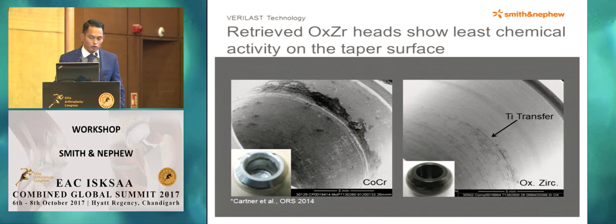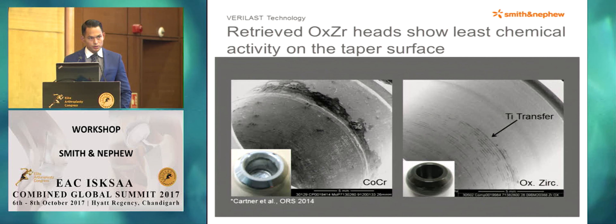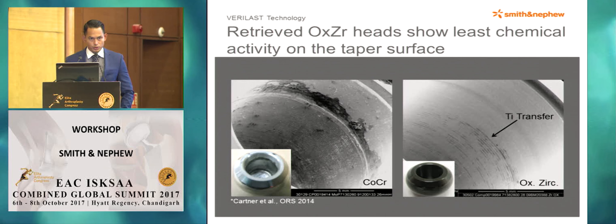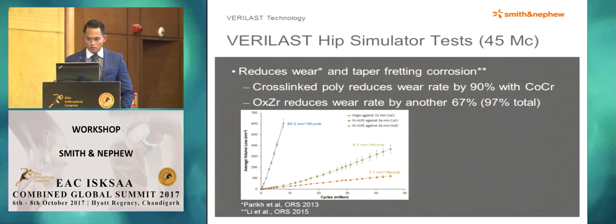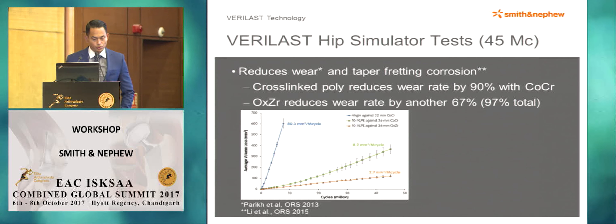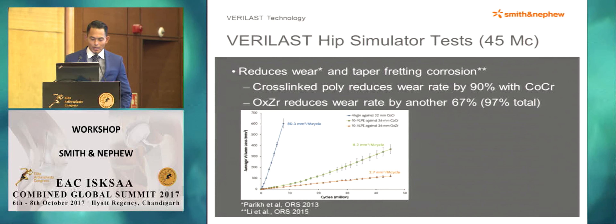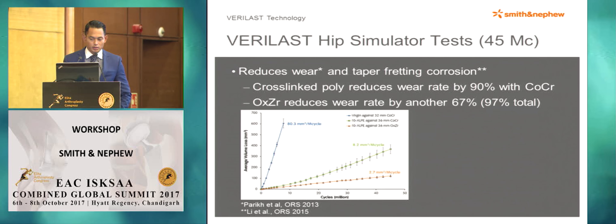The retrieved oxidized zirconium heads showed the least chemical activity on the taper surface. One of the buzzwords in our field these days is corrosion — utilizing this technology, there's less concern for taper corrosion and trunnionosis, as we learned from metal-on-metal bearings. In terms of hip simulator tests, this reduces wear and taper fretting corrosion. Cross-linked polyethylene reduces the wear rate by 90% compared to cobalt chromium, and oxidized zirconium demonstrates a further reduction in wear rate by 67%, leading to 97% total.